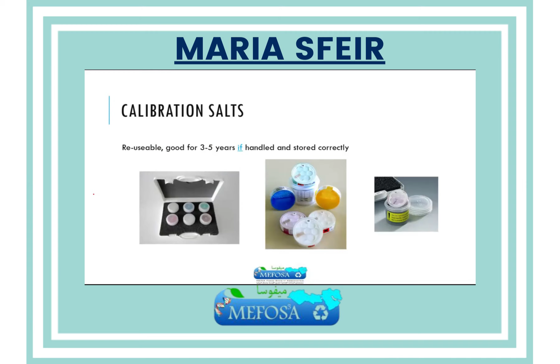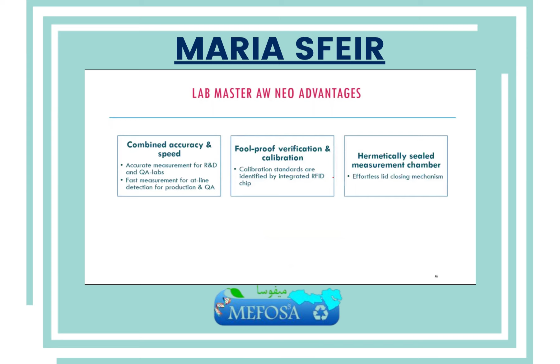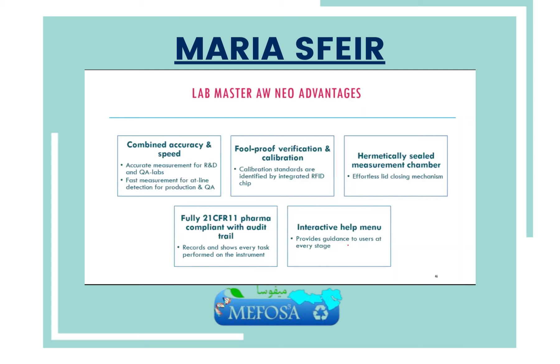The advantages of the LabMaster Neo, which is the most advanced device: we have combined accuracy and speed. We get accurate measurements for R&D and QA labs and fast measurements as well. We have foolproof verification and calibration because calibration standards are identified by RFID chip. The chamber is hermetically sealed. It's compliant to the FDA 21 CFR 11 with audit trail. It can record and show every task performed on the instrument so that we can get a PDF about it and submit it to the FDA. We also have an interactive help menu that provides guidance to the user at every stage, so it's very easy to use.